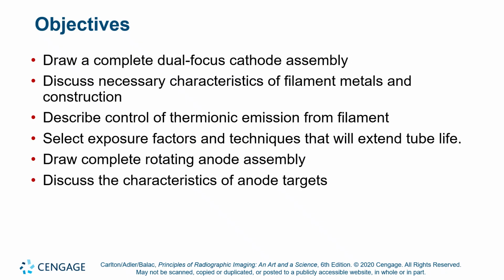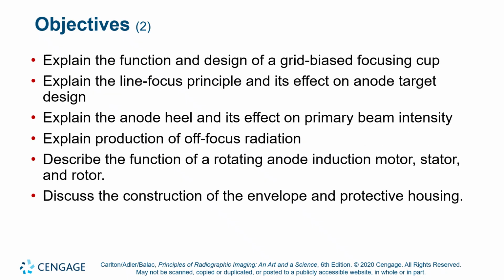Okay. And then characteristics of anode targets. Basically, whatever makes for a good filament also makes for a good target anode. So, yeah, tungsten's involved in both cases. Function and design of a grid biased focusing cup. That's a special new re-engineering of the focusing cup that has come about in the digital age, so we can get a high frequency pulsed X-ray beam, okay, like a machine gun X-ray beam.